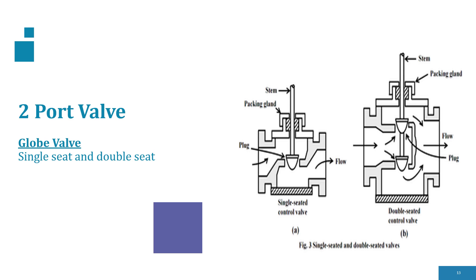A double-seated valve is a top and bottom guided valve; these valves have two plugs and two seats. In this type of valve, the line pressure acts upward on one plug and downward on the other, and because of this the force is balanced. These valves are used for high-pressure applications.